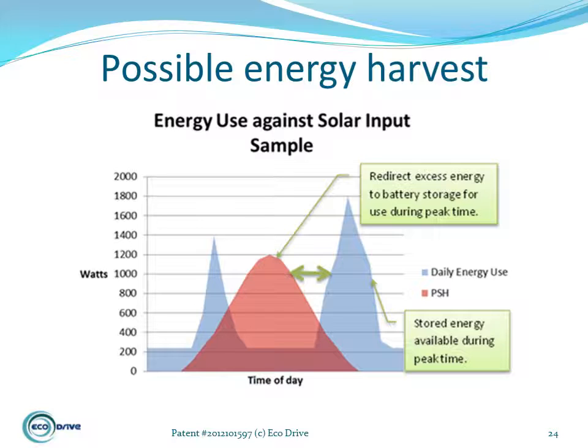In this model we set out to achieve and overcome the limitations of the buffered models highlighted in models 1 and 3, whilst achieving as close as possible to standalone without the expense of large batteries. In this stage the array is sized to charge the batteries at their maximum rate, with the aim of enabling the array to soak up some of the installation's daily loading, as well as moving some of the energy to be used when the array is not operative, as shown in the slide.